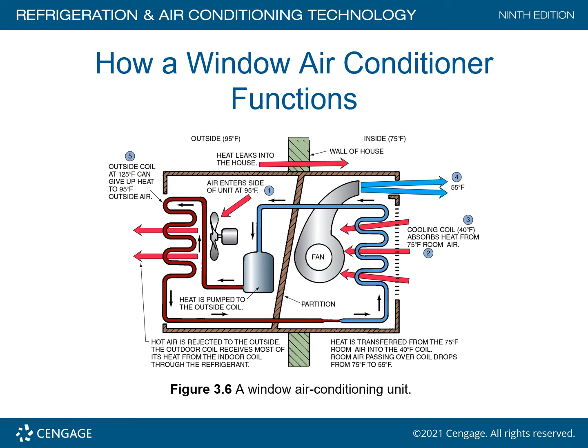Now, typically, what am I looking for as far as the split between the temperature in and the surrounding air? I think a good rule of thumb would be this, 10 degrees. So in other words, let's say that it's 95 degrees outside and the fan is blowing air across that condenser coil. You should see at least 10 degrees increase from the surrounding air. And that's just another rule of thumb that I've used, and it works very well. Hopefully this answers your questions as far as the window air conditioning unit. Remember, fan speed plays a big deal when it comes to regulating how much airflow is coming across the evaporator. If the airflow is too low, this thing's going to freeze up. If the airflow is too high, you're not going to get the correct cooling ratio.